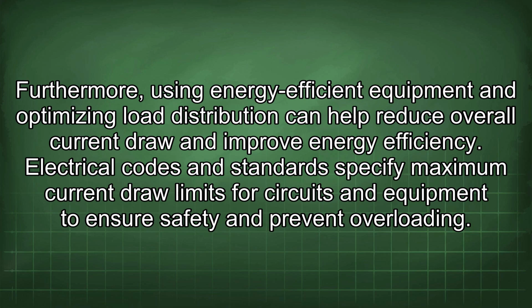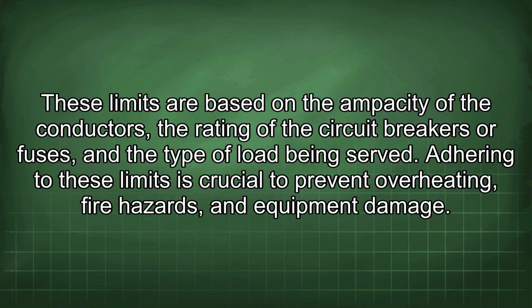Electrical codes and standards specify maximum current draw limits for circuits and equipment to ensure safety and prevent overloading. These limits are based on the ampacity of the conductors, the rating of the circuit breakers or fuses, and the type of load being served. Adhering to these limits is crucial to prevent overheating, fire hazards, and equipment damage.